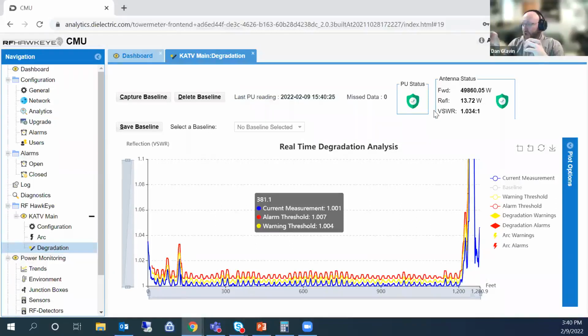What this antenna status does, and how it changes to failure, is that in the presence of a high VSWR, user defined, but in the absence of a transmission line degradation or arc, it is determined that the issue lies at the antenna level. But an increased VSWR simultaneous to a degraded component in the transmission line, or a detected arc, does not actually indicate an issue exists at the antenna level. So this forward compatibility in the RFHawkeye now allows us to monitor the entire system, not just the transmission line.